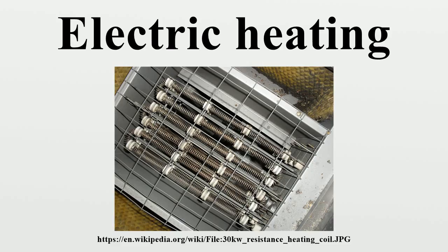A poorly insulated hot water cylinder will increase running costs because a consumer must pay for electricity used to replace lost heat. Electric shower and tankless heaters also use an immersion heater that is turned on with the flow of water. A group of separate heaters can be switched in order to offer different heating levels. Electric showers and tankless heaters usually use from 3 to 7.5 kilowatts.